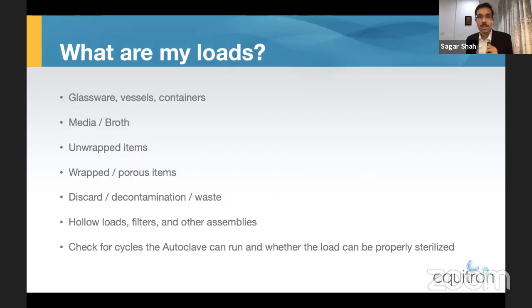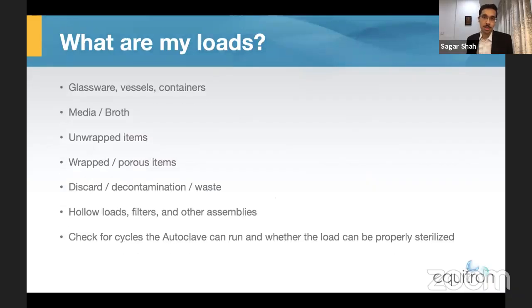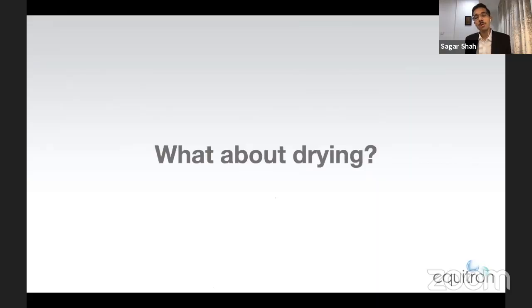But there is one other point that you need to consider as well, and that is the need for drying. Some autoclaves are readily equipped with the option of drying a load. And again, you have two options here, normal drying and vacuum drying. Some non-vacuum autoclaves may have normal drying, in which you would typically get around 80 to 85% drying efficiency. This is for loads such as glassware and non-porous loads. But if you're looking at garments, or at glassware as well, and you want 95 to 100% drying efficiency, then you would need to look at a vacuum autoclave option itself.